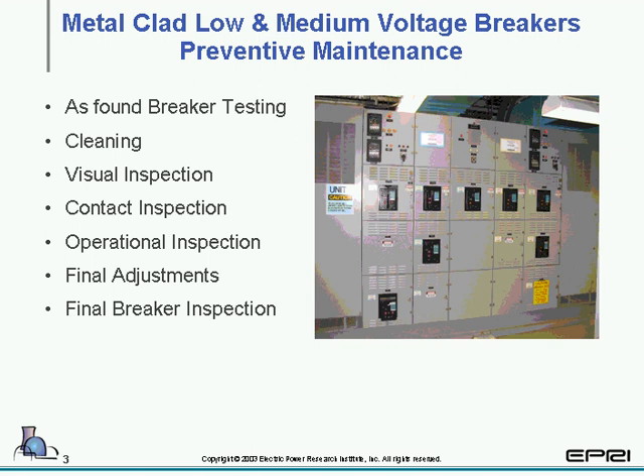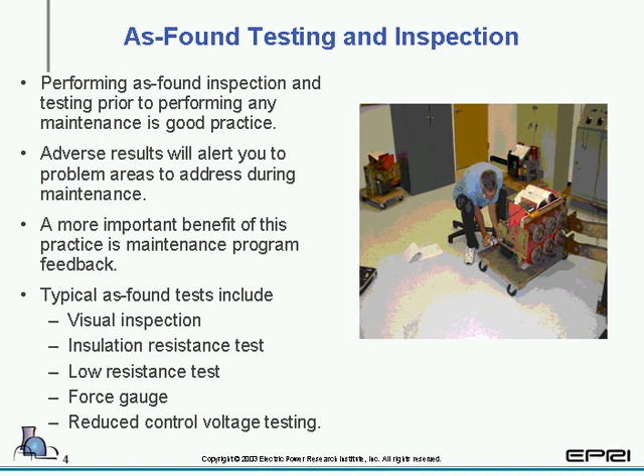As far as metal clad low and medium voltage preventative maintenance, we're going to be looking at as-found testing, cleaning, visual inspection, contact inspection, operational inspection, final adjustment, and final breaker inspections. As-found inspections and testing: performing as-found inspections and testing prior to performing any maintenance is good practice. And you'll see at the very bottom, we have a list of items, and for those of you taking the test, you might want to remember that. But these items, as a minimum, should be followed. And if you find any of the test data that is outside of what you expect to see, you should do some further investigation to see if there's a problem.